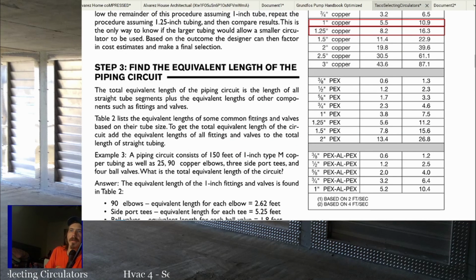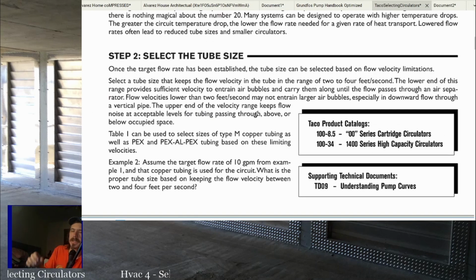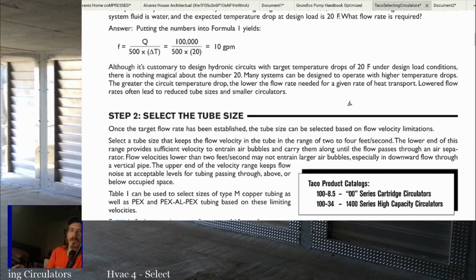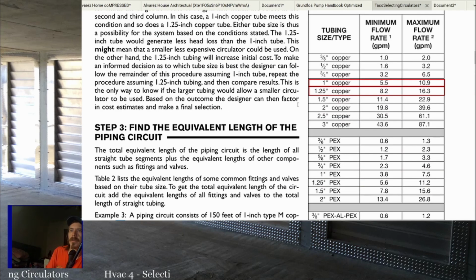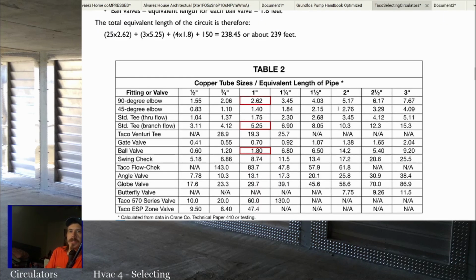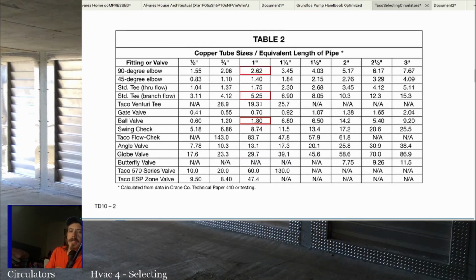And again, I know a lot of you guys probably aren't going to be designing boiler systems on a regular basis, but we're going to learn to do load calcs this year. It's very possible you'll be designing a boiler system at some point in your career. But even when you're doing replacements, having a good idea of how the pipes run in the system helps. You're going to know the pipe size because you'll see what the main size is coming back to the boiler. I'll bet you a dime to a dollar if you just pay attention, you can guess how that zone is run because you know where the piping starts in the boiler system.